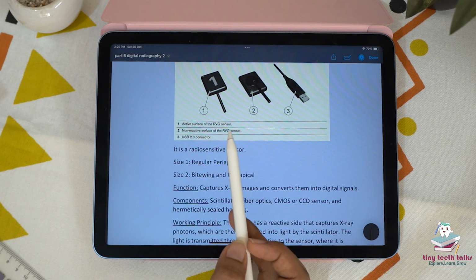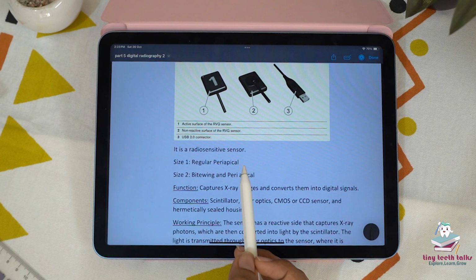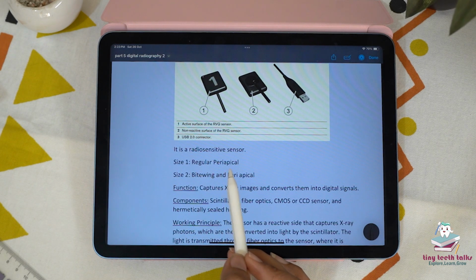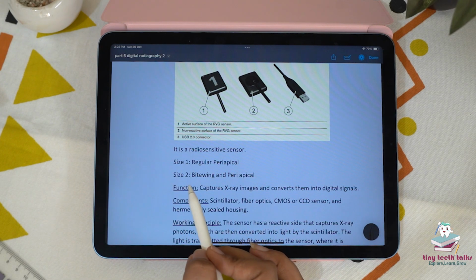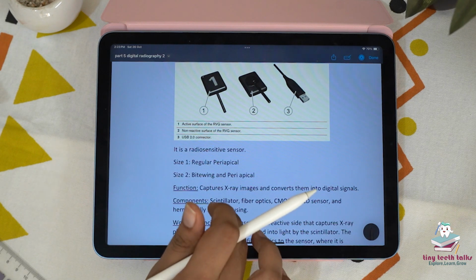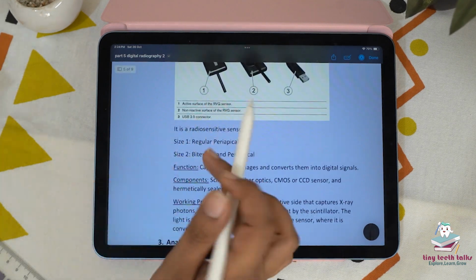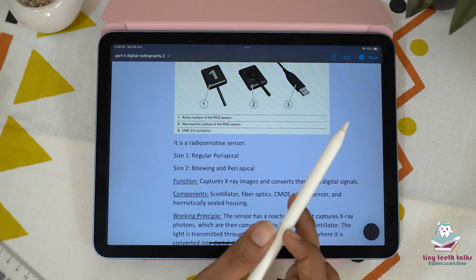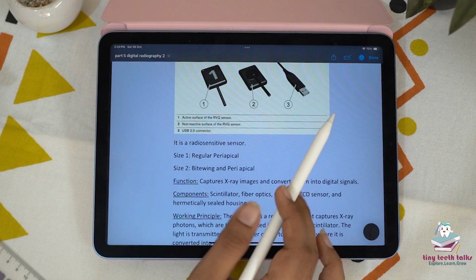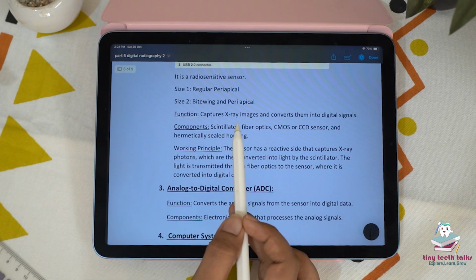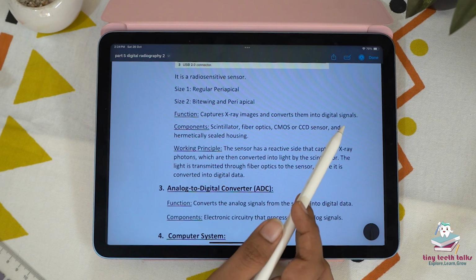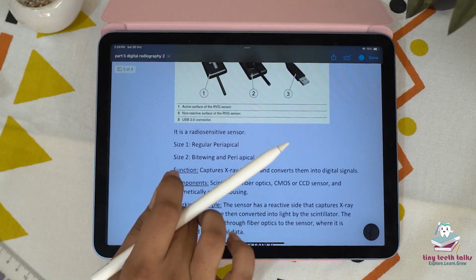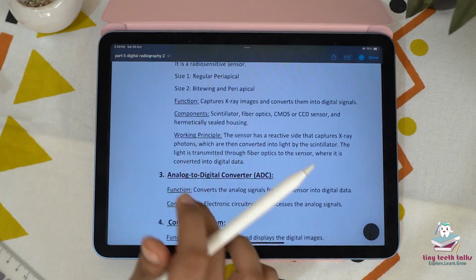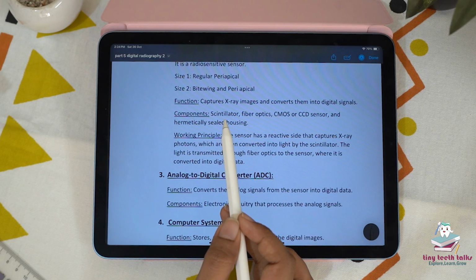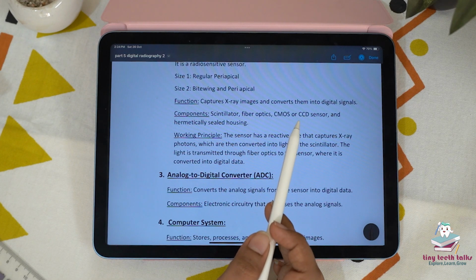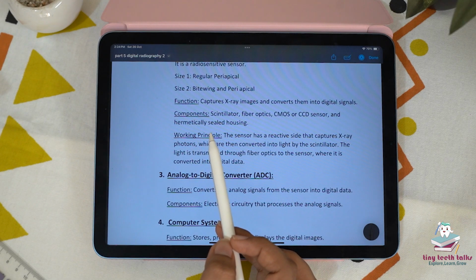Second is the RVG sensor. It is a radio-sensitive sensor. It has size 1, which is for the regular periapical radiograph, and size 2, which is for the bite-wing and periapical radiographs. Also, it has an active surface, a non-reactive surface, and a USB 2.0 connector. The function is to capture X-ray images and convert them into digital signals. Now, this RVG sensor itself has components: first the scintillator, fiber optics, CMOS or CCD sensors, and a hermetically sealed housing.